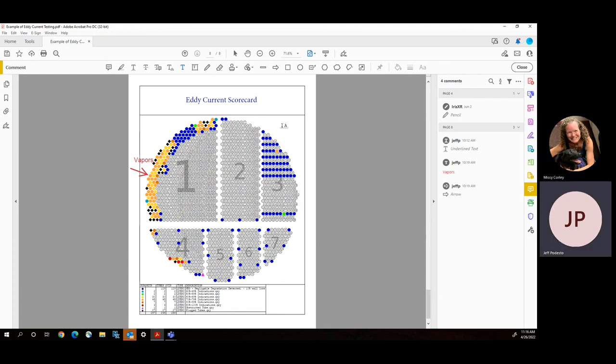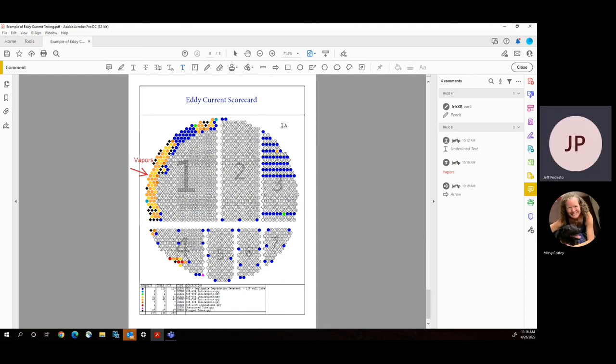Yeah. If you look at just this customer right here where the scorecard's up, a replacement calandria is in the probably $3 million area by the time it's installed and running versus probably in the end, $50,000 for testing, another less than $50,000 for plugging and repairing, and with the knowledge that they can probably run for another 10 or 15 years pretty comfortably with a $100,000 investment.